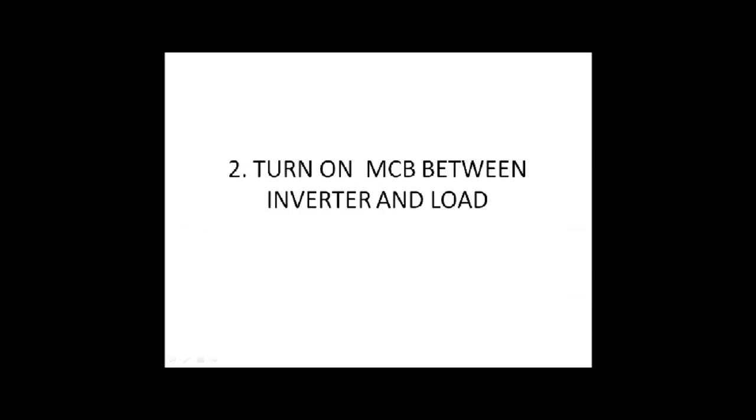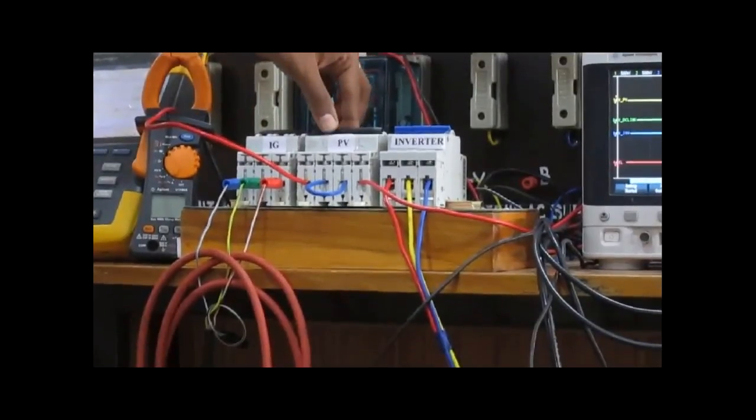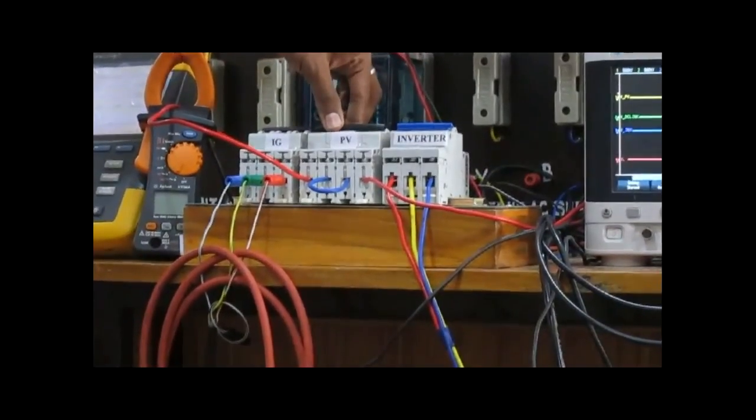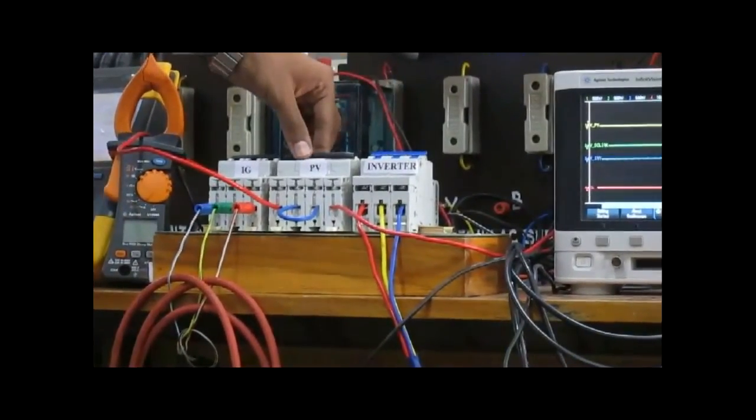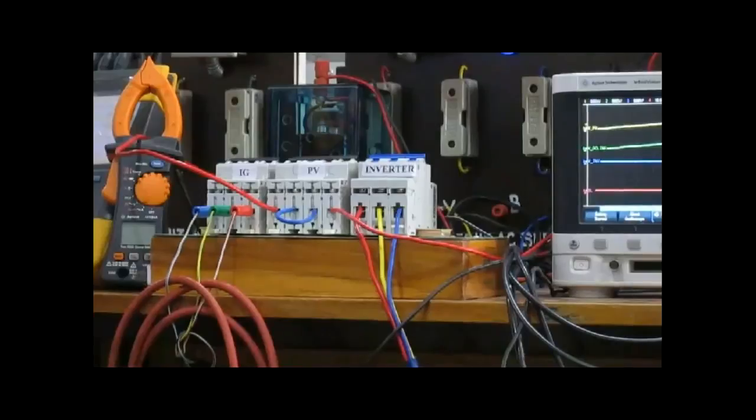Some sequence of operation is listed on the screen. First we turn on the PV MCB. Then we turn on the MCB between inverter and the load. Then we turn on the IG MCB. Once the wind speed or the speed of the wind turbine increases the cut-in speed, it automatically is synchronized with the system which will be demonstrated now.